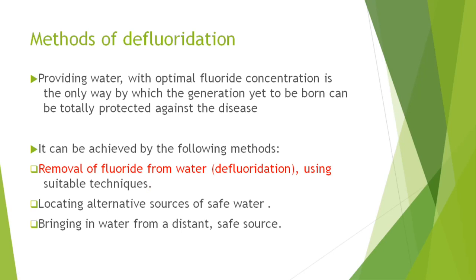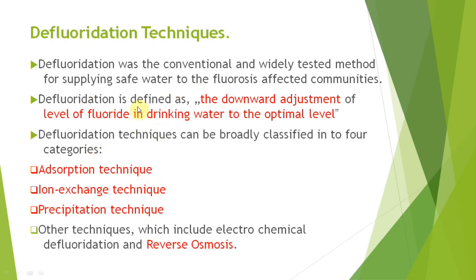By definition, defluoridation is a downward adjustment of the level of fluoride in drinking water to the optimal level. Fluoridation is upward adjustment, whereas defluoridation is downward adjustment to the optimal level of 1 ppm. The common methods are: adsorption technique, ion exchange technique, precipitation technique, and reverse osmosis. Adsorption keeps some material in the water and fluoride gets adsorbed to the surface; ion exchange replaces fluoride ions with cations and anions.